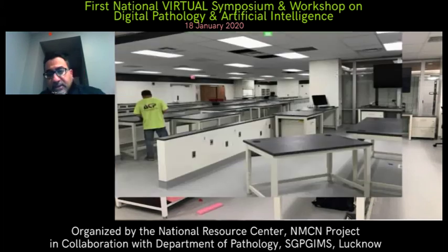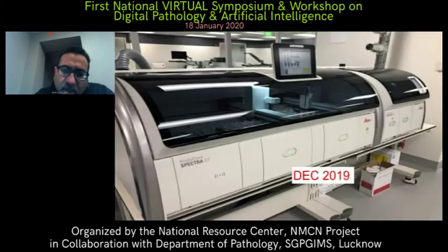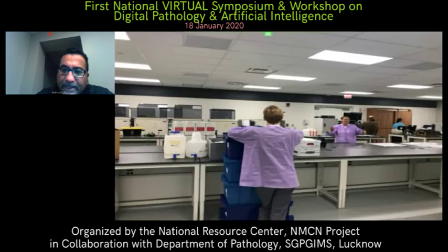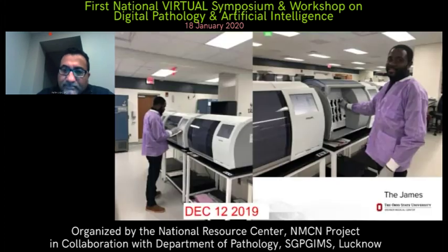And then this is a new automated histology stainer and cover slipper that we bought. So tissue could go in to one place, slides could be stained, cover slipped, and directly moved to the scanning systems. So now the lab is fully operational, and the scanners are working day and night. And we've already started to review.